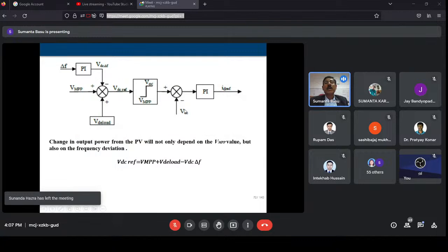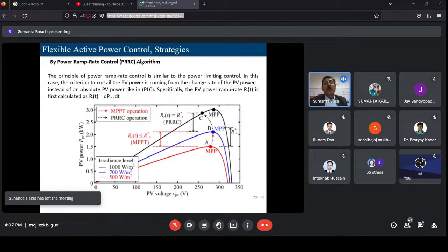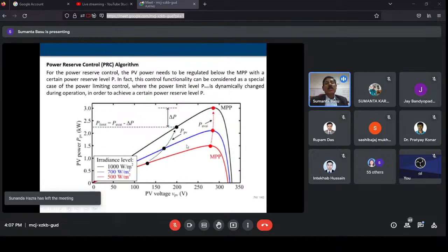The second algorithm is the ramp rate control algorithm, or PRRC algorithm. Here it is similar to the PLC, but for fast actions, the rate of change of that demand acts as a feed-forward signal to the inverter or converters to modify the MPPT algorithms there. So this is called your power ramp rate control. Another is the power reserve control algorithm. This power reserve control algorithm is also very useful under such circumstances, where it is the power reserve level.